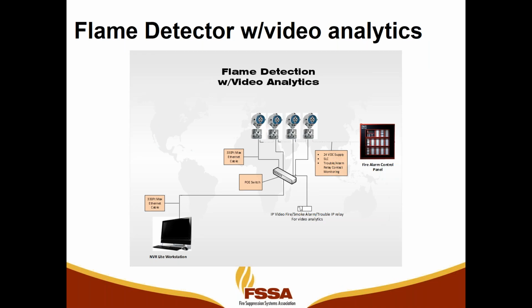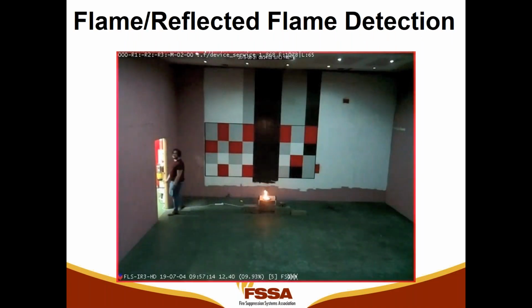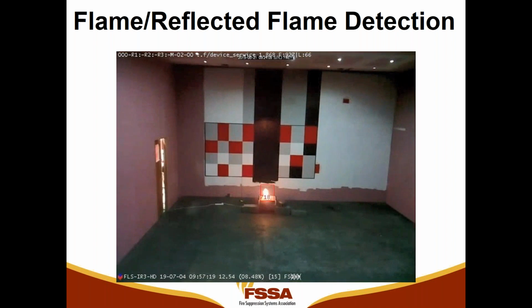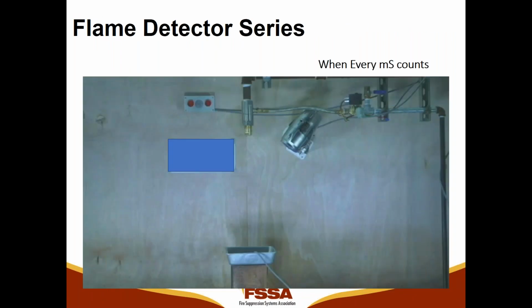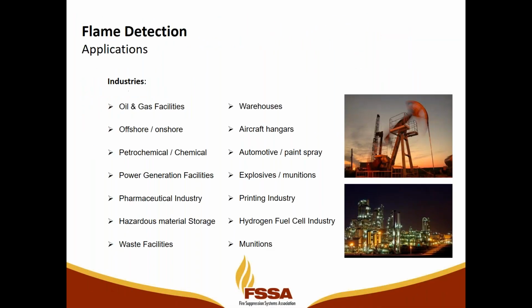So in here, the same thing, fire alarm panel, 24 volts DC, contact monitoring, and then Ethernet run non-PoE, the power is from the panel, and then down to an NVR for recording, or a server that's analyzing the image. There's also a relay, an IP relay that's used for the analytics alarms. So when the triple IR is in alarm, you'll see a red flashing on the outside of the screen. This is an indication of an alarm for the triple IR. And then the video analytics also is an alarm. Sorry about that.